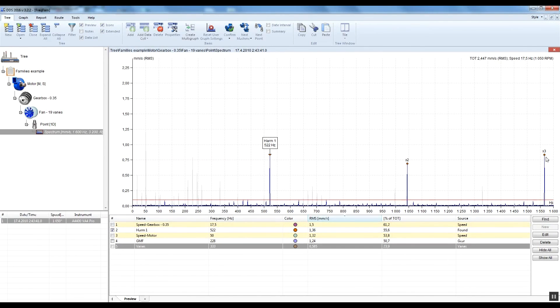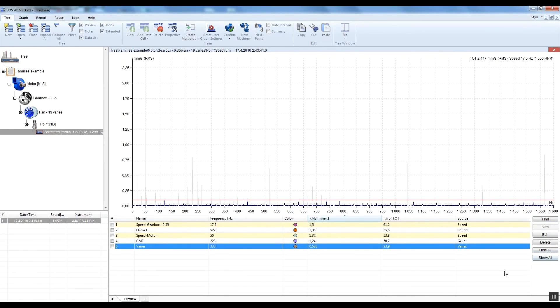Now I should speculate about the source. The family function is so useful because it can describe all known sources in the machine. Then I can hide them to look at the residual spectrum — the lines with known sources do not obstruct my view. If I hide all known families, then only peaks under the threshold remain in the spectrum. It means the complete spectrum interpretation was done. Thank you for watching this tutorial.